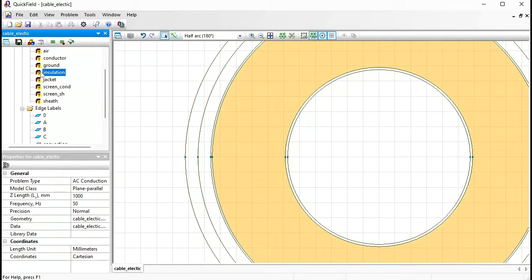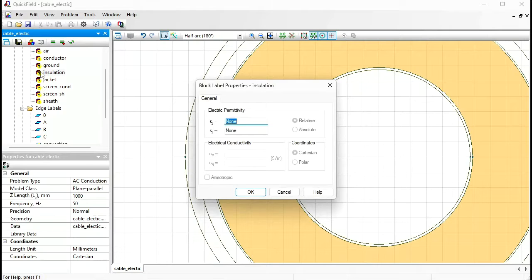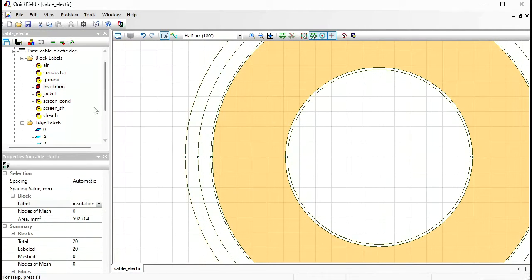For the insulation, the electric permittivity is 2.5, and to be able to calculate the dielectric losses in the insulation, I should specify the apparent value of the electrical conductivity, which is 6.95 picosiemens per meter. Pico means times 10 to the power of minus 12. Okay, and the same properties I'm going to assign to the semiconducting layers.